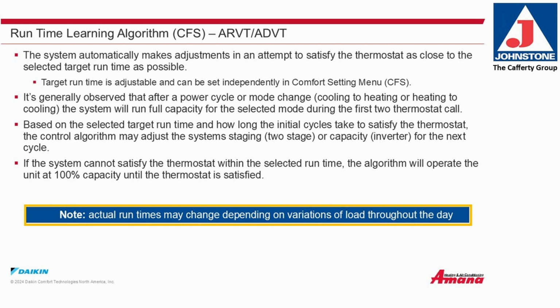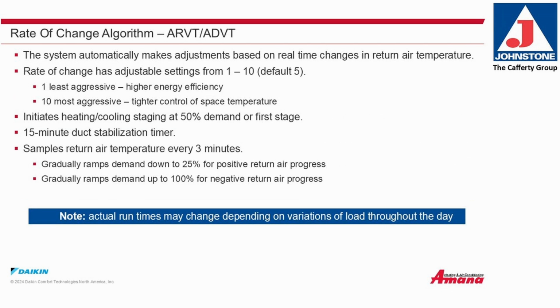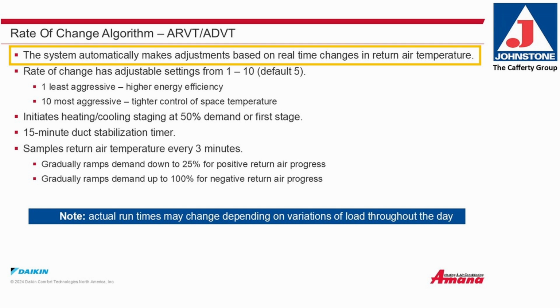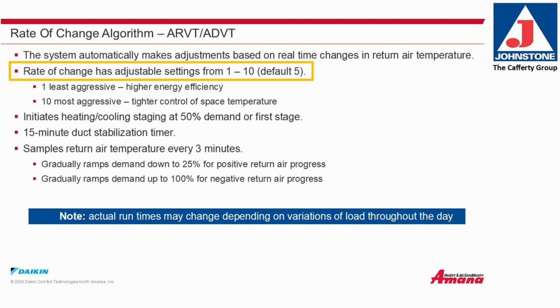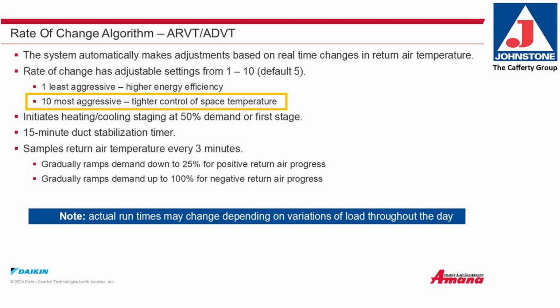Rate of change algorithm. The system automatically makes adjustments based on real-time changes in return air temperature. The rate of change has adjustable settings from 1 to 10, default is 5. 1 is the least aggressive, higher energy efficiency. 10 is the most aggressive, tighter control of space temperature. Initiates heating and cooling staging at 50% demand or first stage.